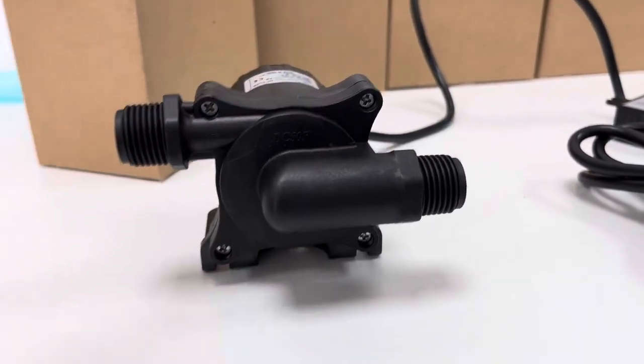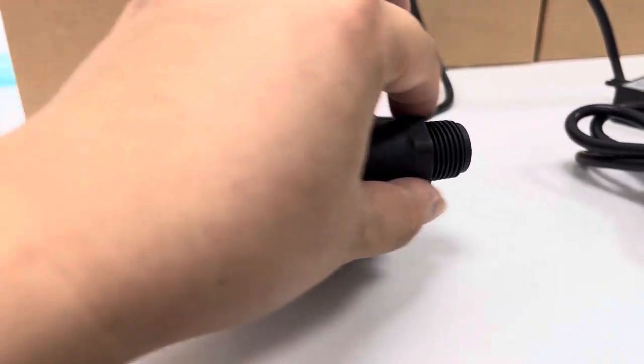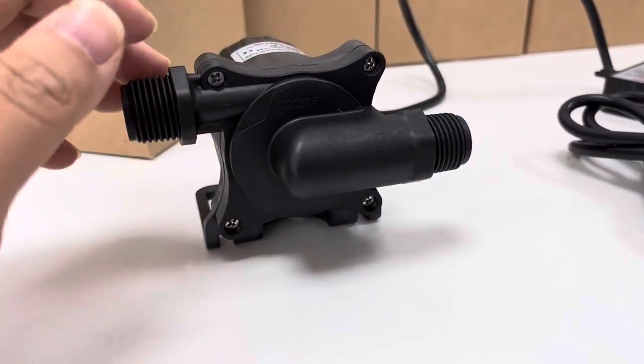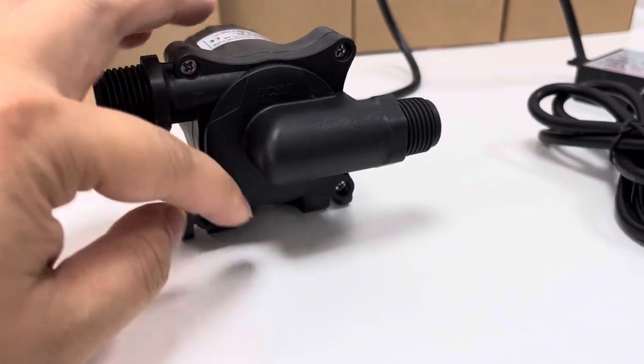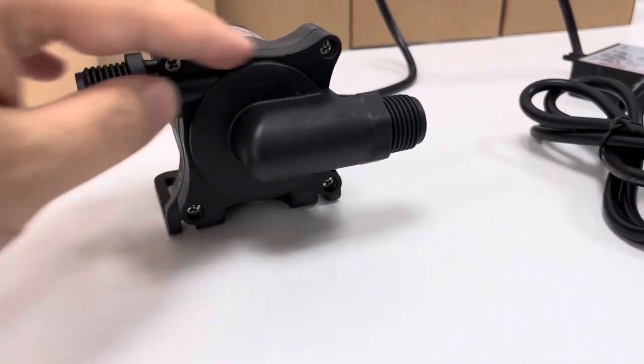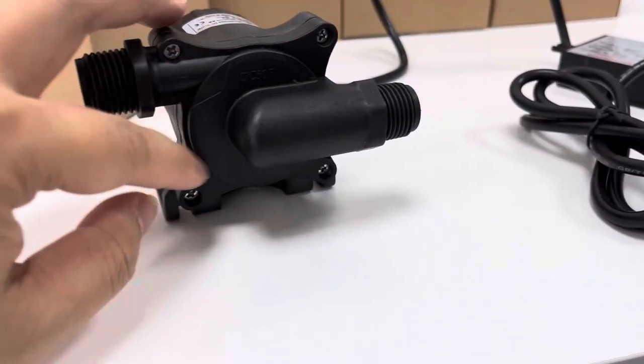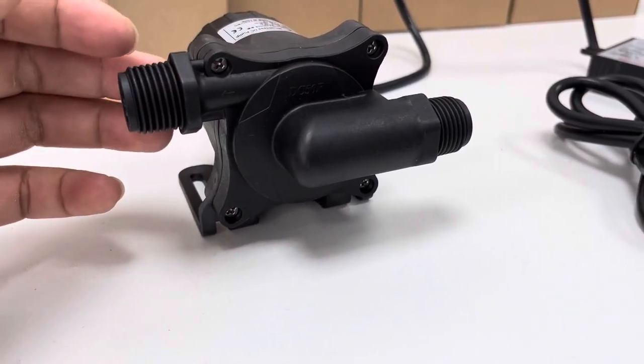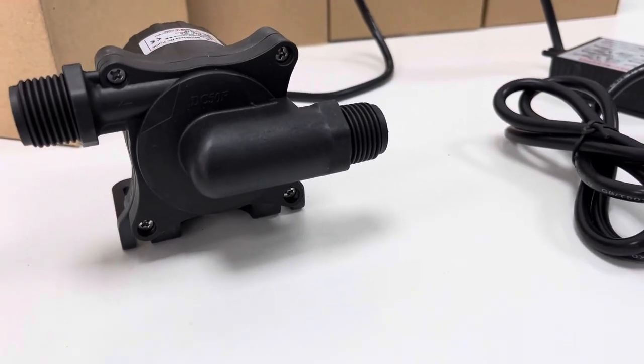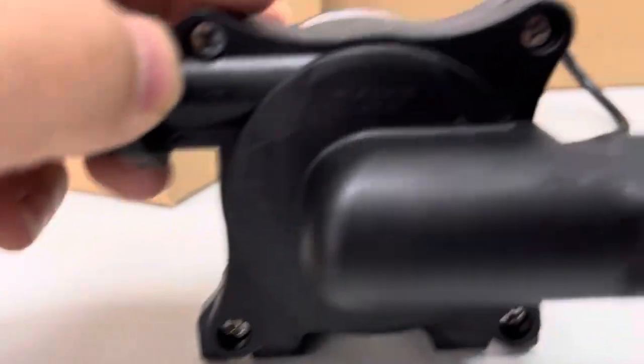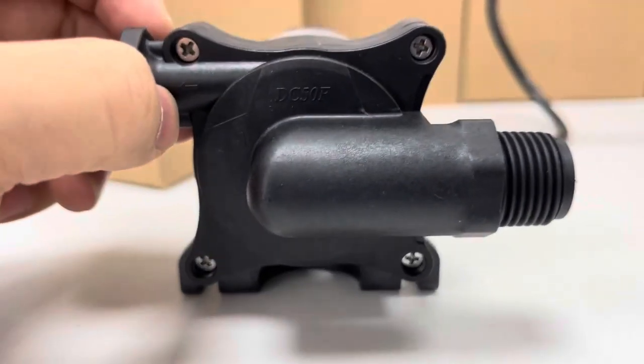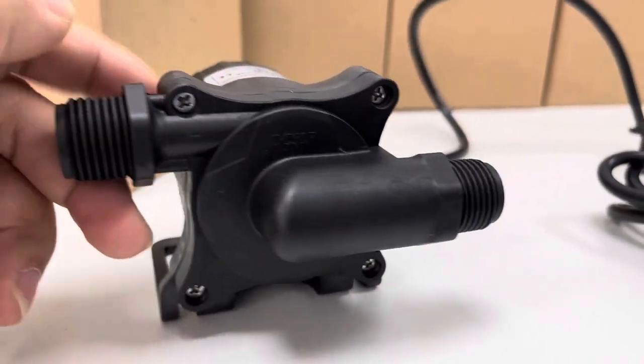This is the front side. We look at this pump, right? This is outlet. This is inlet. Actually, it is quite simple to distinguish which is inlet, which is outlet, because the pump works by the centrifugal force or high-speed rotation of impeller. If we see this, this is a circle of circulation. And this will be outlet based on the centrifugal force direction. The other will be inlet. Our DC-50F is marked here, printed here. And this is the arrow. This arrow shows the directional flow. Of course, it is outlet.